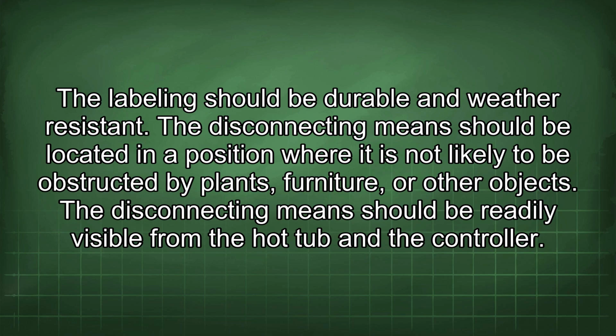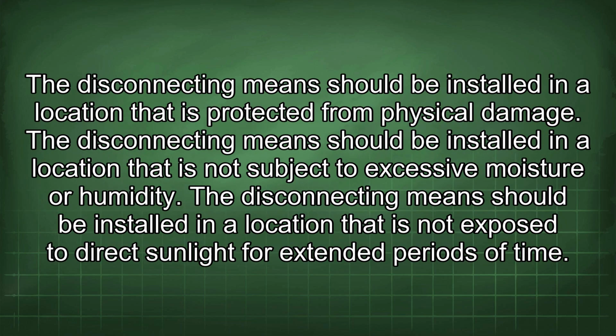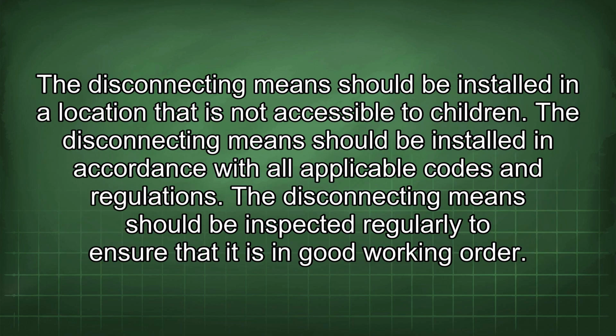The disconnecting means should be located in a position where it is not likely to be obstructed by plants, furniture, or other objects. The disconnecting means should be readily visible from the hot tub and the controller. The disconnecting means should be installed in a location that is protected from physical damage, is not subject to excessive moisture or humidity, is not exposed to direct sunlight for extended periods of time, and is not accessible to children.